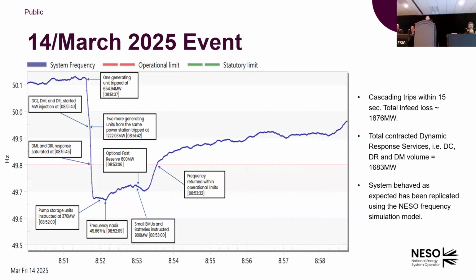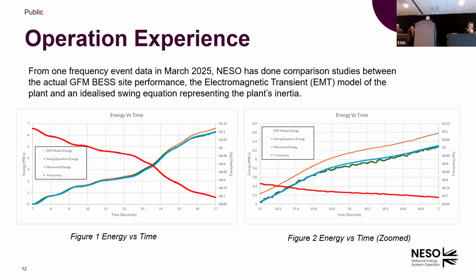Anyhow, the frequency dropped from 50.1 all the way to 49.7, so it's still sizable. And we can see how the grid forming battery behaves. When you calculate the rate of change of frequency of that event, it is somewhere around 0.1 hertz per second, so the frequency keeps on dropping. One of the interesting things is that because of all this fast frequency response from the batteries, the speed of the frequency drop is very slow, and the frequency nadir is much higher than it would be without fast frequency response.